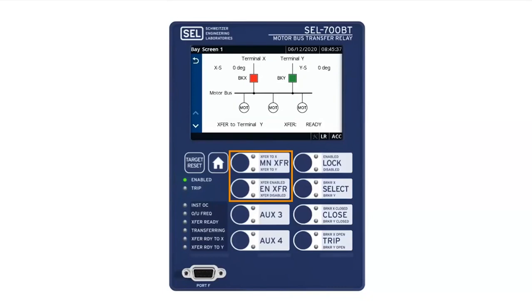So obtaining a spin down characteristic, I think it's simple enough. It's just if at some point you disconnect your motors, then you can see what that is. The other one is doing modeling, or having some idea of how long those motors will take to spin down and for how long you will have some voltage support on the system. So there may be cases where you don't know anything about the system, and in those cases you will need to do some extra measurements. Basically, you can set the relay without knowing it, but you still need to know the breaker close times.